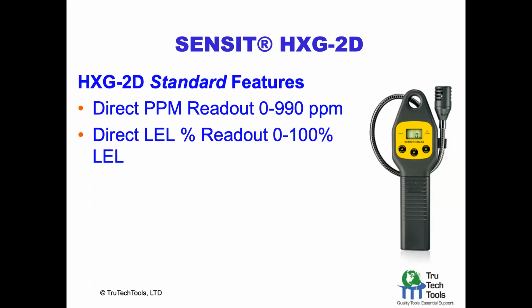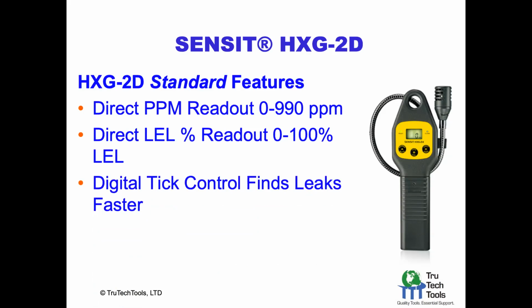The next measurement it has is a direct LEL, which is a lower explosive limit readout that goes from 0 to 100% of the explosive limit of the gas it's calibrated for. And again, we'll go through a chart of all that and what that means. There's a digital tick control that helps you find leaks faster. Basically, it's a resettable threshold that you can put in the product. So it's sort of like, if you're familiar with the Leakator 10 from Bacharach, great product. That product has a thumb wheel dial to allow you to adjust the clicking threshold at which it's sensing the gas. You're actually changing a control inside the instrument. This one does it with a digital control.